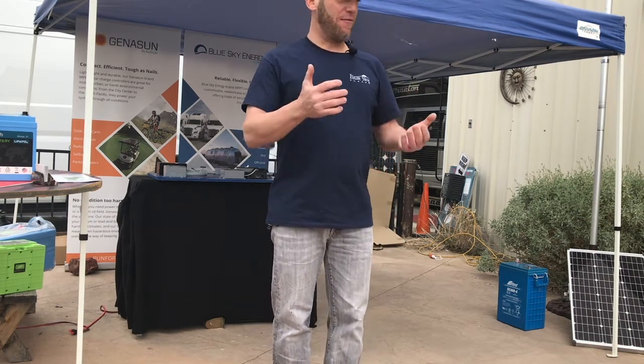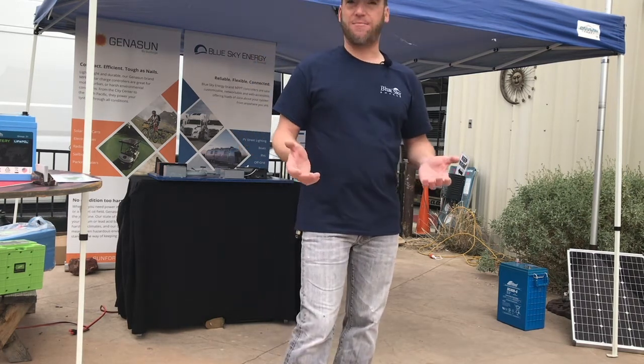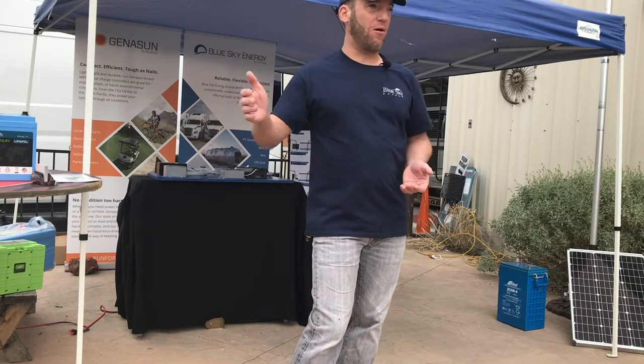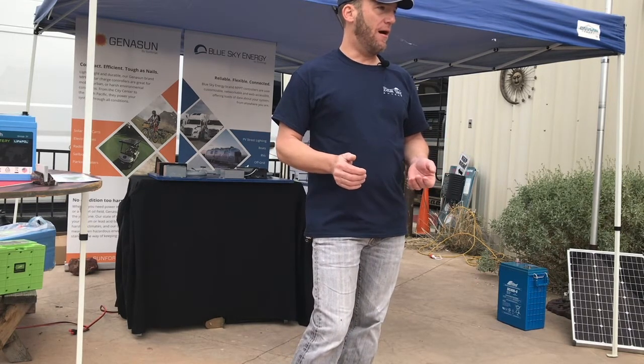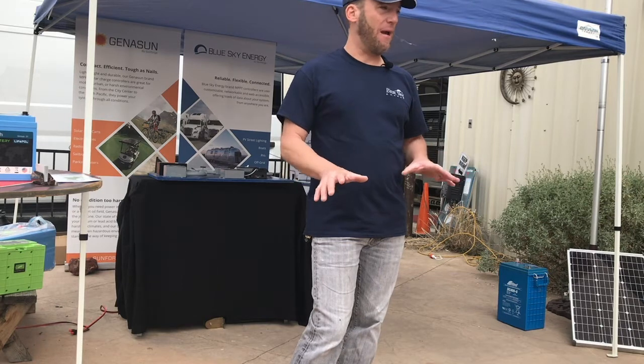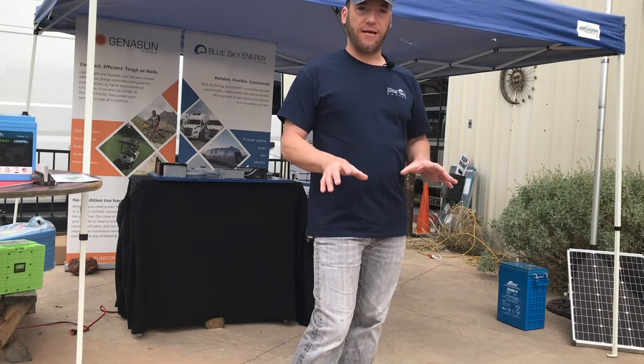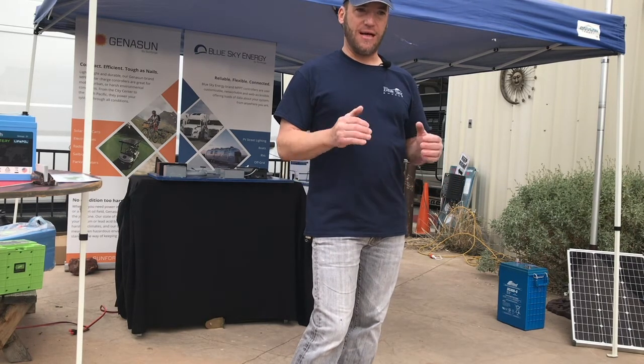Different batteries have different transition set points. Lifeline specifies 0.5 amps per 100 amp hours of capacity, while our factory default is about 1.5 amps, which is more suitable for lead acid batteries. So that's a much better way to do it.